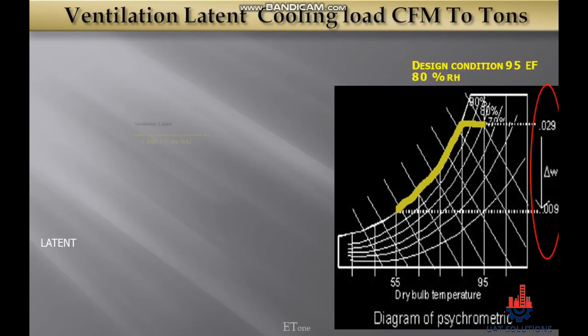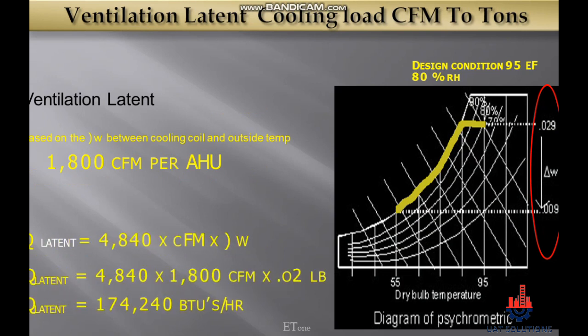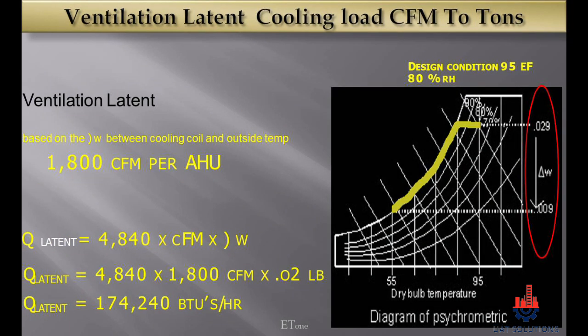The next step is to convert ventilation latent cooling load CFM to tons of refrigeration. The latent cooling load is 1,800 CFM, and the factor value is 4,840. The pound of moisture in the air, measured on-site as per the delta T required, is 0.02. Multiplying 4,840 by 1,800 by 0.02 gives 174,240 BTU per hour for ventilation latent heat.